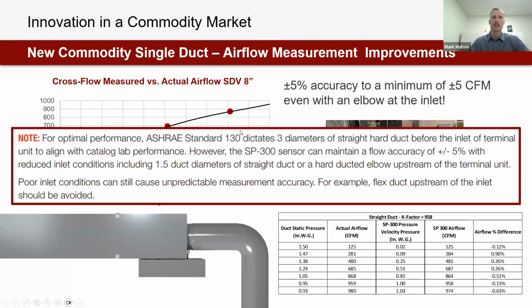So our IOM now states, hey, ASHRAE likes 3 duct diameters. We'll take 1.5 or an elbow directly upstream, and we'll still have plus or minus 5%. So, some other incremental improvements there, just because we had an opportunity to do a lot of testing on the product, and we decided to kind of push the limits of our equipment a little bit.